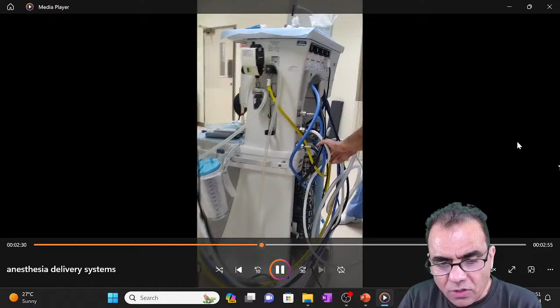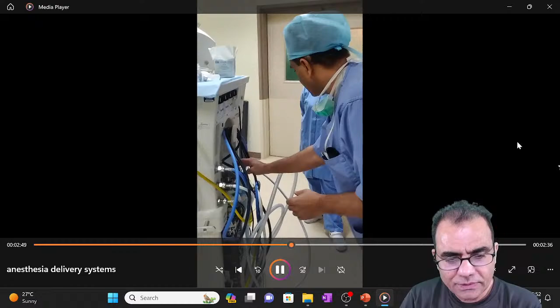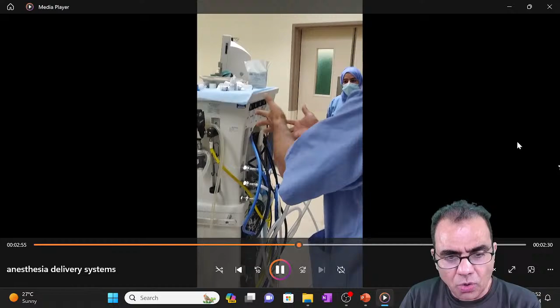And obviously here, what you are expecting is the pin index system. So at the back of the machine, it will be the pin index system, which is going to prevent the wrong fitting of cylinders. Fine. And after that, there will be pressure reducing valves inside the machine. So now I'm coming to the front side of the anesthesia machine.